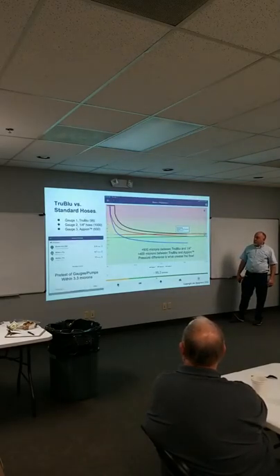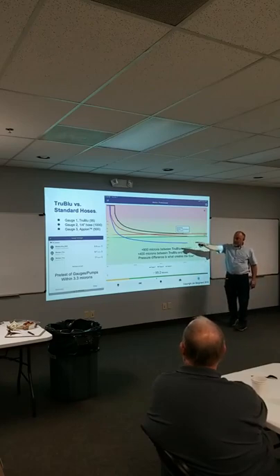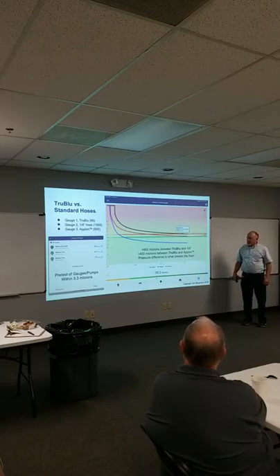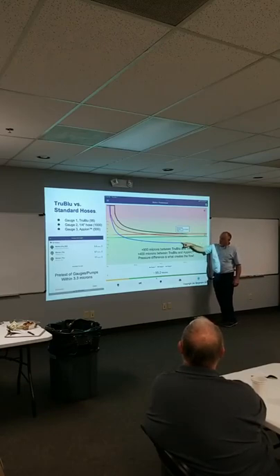So you look at a TruBlu hose versus standard hose. I had 3 vacuum pumps from Fieldpiece, hooked them all up to the vacuum gauges. All of them could pull down south of 10 microns: 5, 4, 8, 7, 7, 7. That's a pre-test. They're all within 3 microns of each other. Now I want you to look at this for just a minute, because this is a 1/4 inch hose, this is an Appion hose, and this is a TruBlu hose.